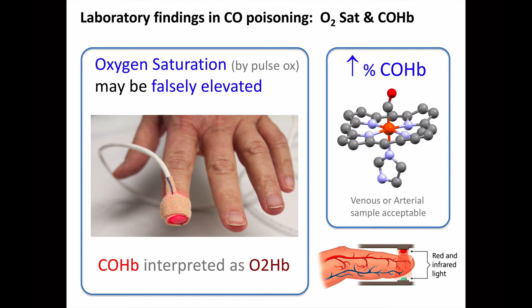Standard pulse oximeters are simple spectrophotometers. They differentiate oxyhemoglobin from deoxyhemoglobin by measuring the absorbance of 2 wavelengths. One is red with a wavelength of 660 nanometers, and the other is near infrared with a wavelength of 940 nanometers. The graph here shows the differences in light absorbance between oxyhemoglobin and deoxyhemoglobin.